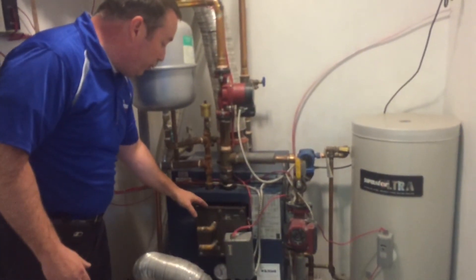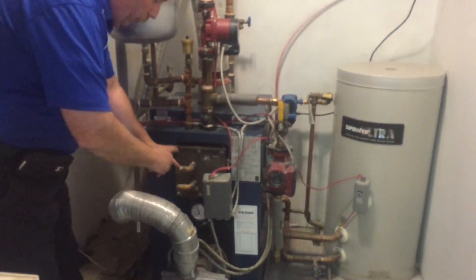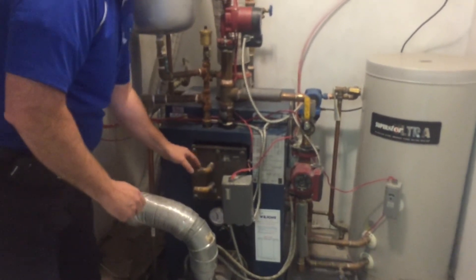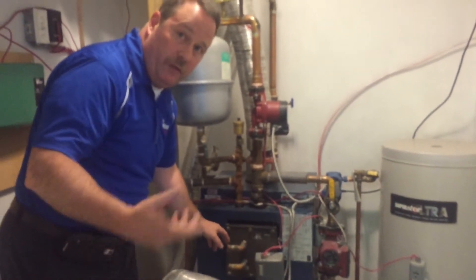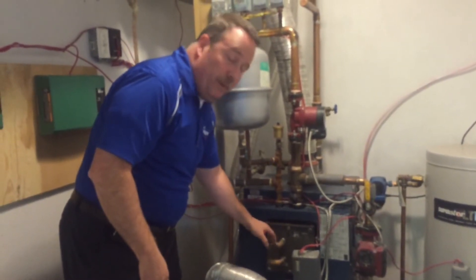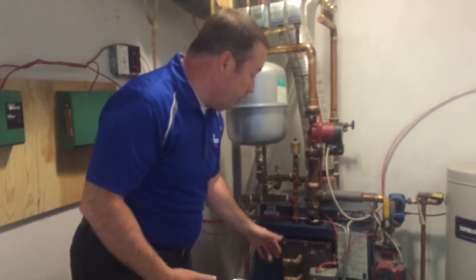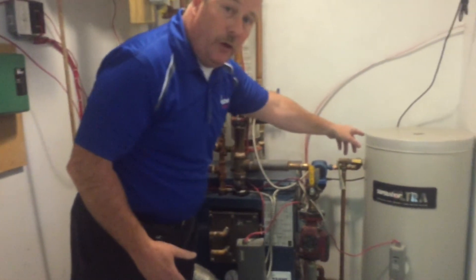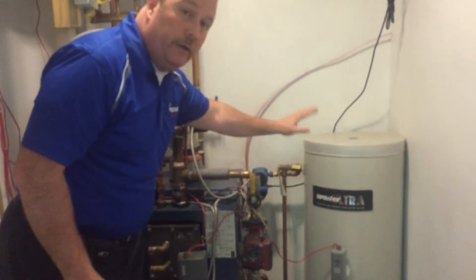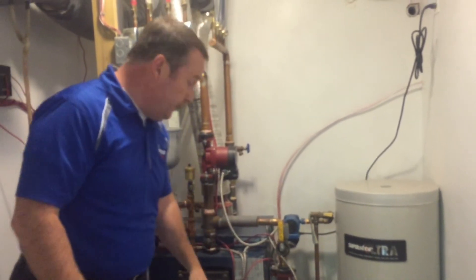This particular one was equipped with what's called a tankless coil. All the tankless coil is, is a coiled up piece of copper that's immersed in the hot boiler water, and that's how you get your domestic tap water for filling tubs and showers. In this particular instance, this domestic coil wasn't meeting the family's needs as far as water production is concerned. So what they've done is they've installed a separate tank called an indirect water heater, which is heated up by the boiler indirectly and stores about 40 gallons of hot water for tubs and showers.